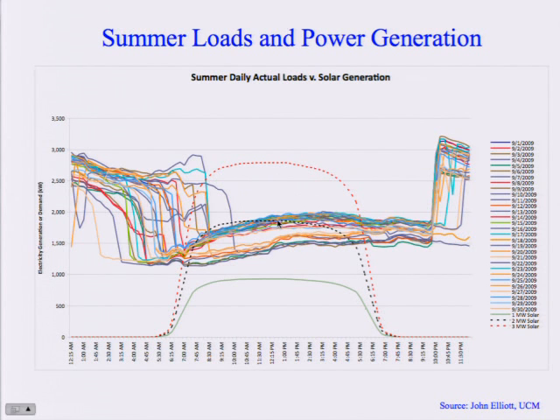These dashed lines are projected lines of what we'd tend to get in summer with a system like that, and these are the loads. Remember I told you we chill the water at night, so the chillers are basically running at night, and that's when you get the big load on campus — maybe 3 megawatts there. It turns on roughly at 10 p.m., goes up, stays chilling during the night when rates are low, and then goes down. The chillers are off, and now you have the normal operation of the campus during the day.